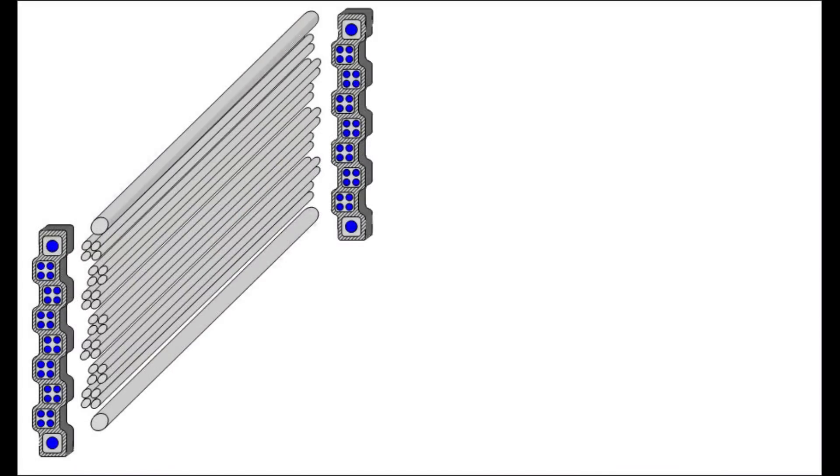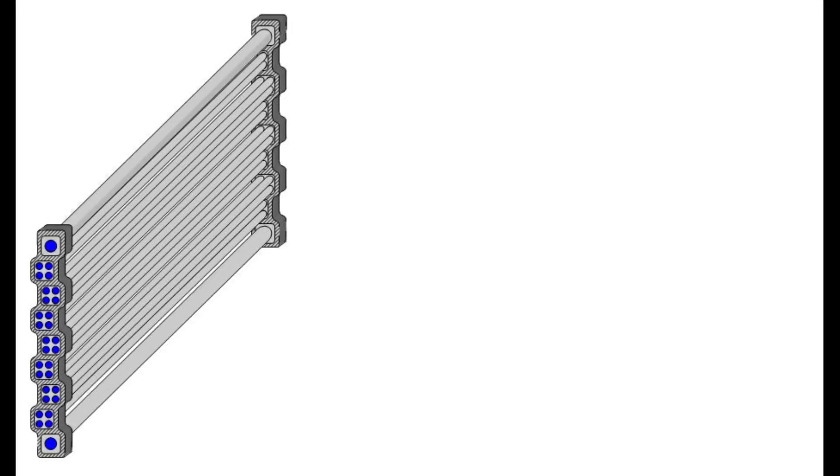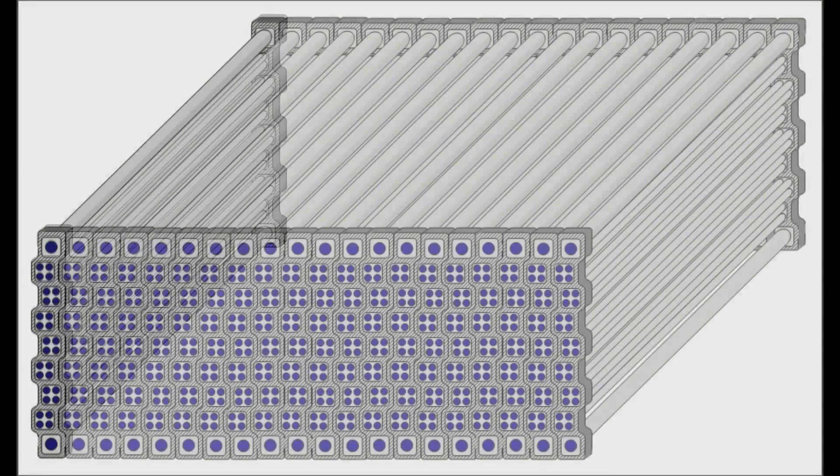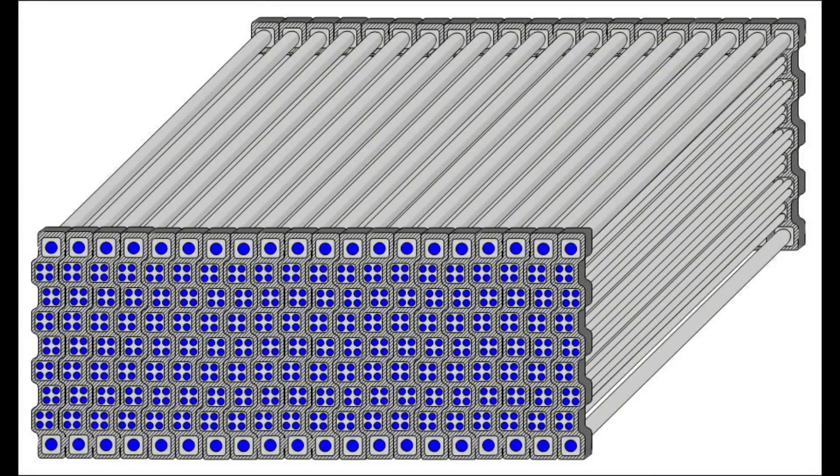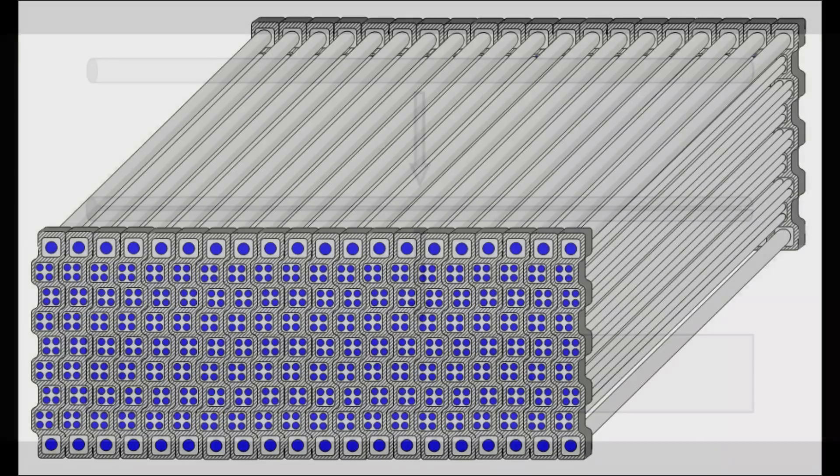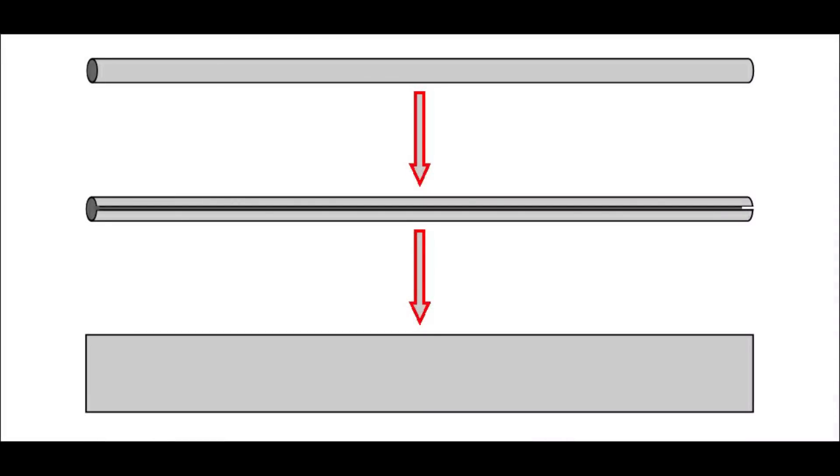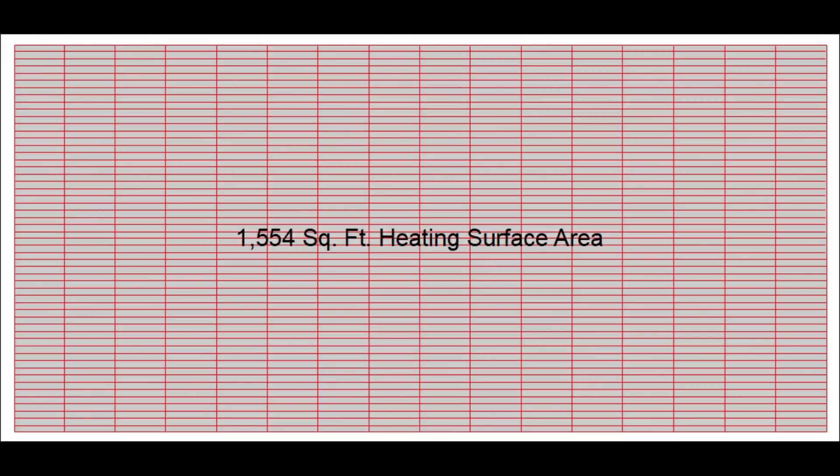The other variable was the surface area of the water tubes in which steam was produced. Tubes were bundled into sets of four that were fed water and discharged steam through headers at each end. Their walls acted as interfaces through which heat from burning gases passed to generate steam. Even though each tube had a small diameter and small surface area, each of Texas's coal-fired boilers contained 892 of them. If you took each tube, split it, and rolled it flat, their combined area equaled 1,554 square feet of tube surface through which heat could pass. That's the same size as the floor space of a medium-sized house.